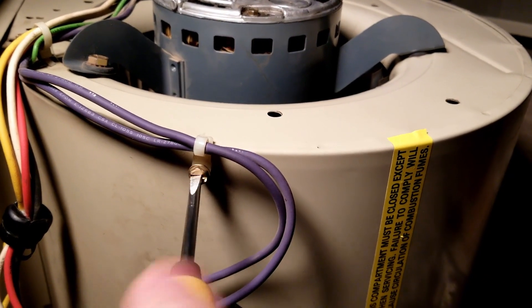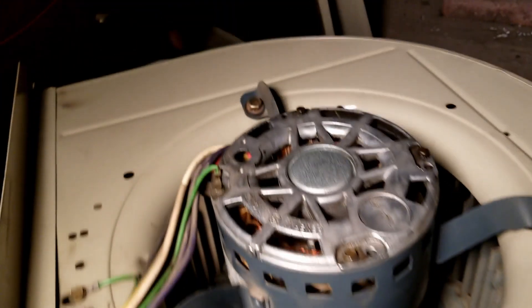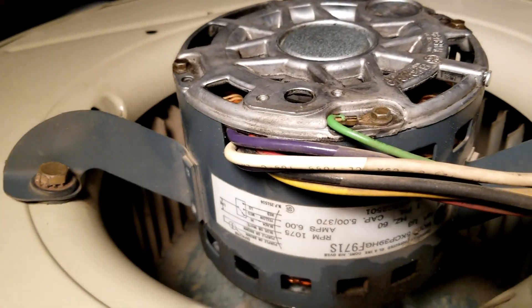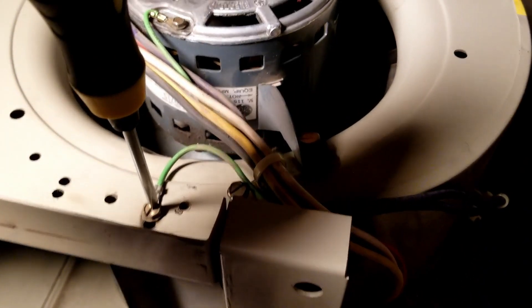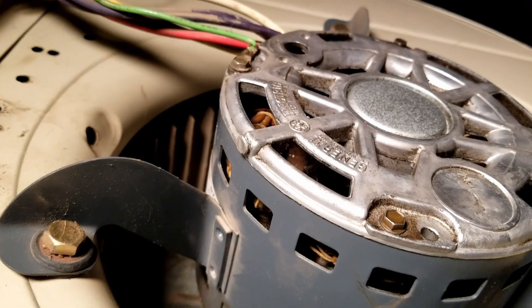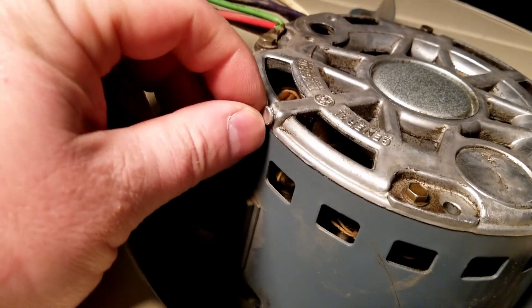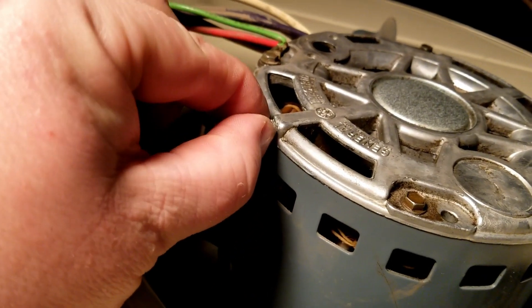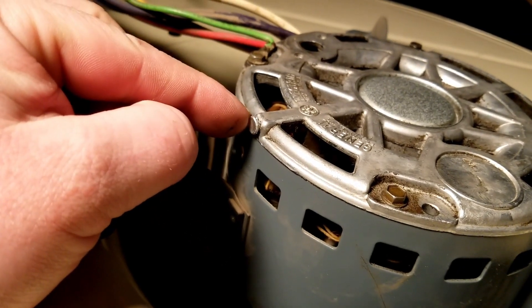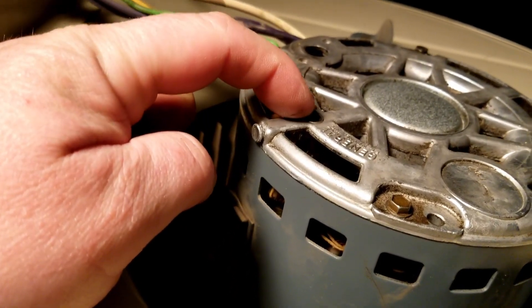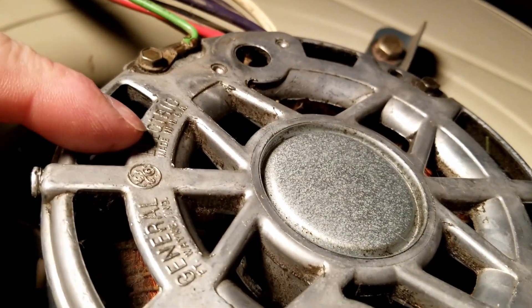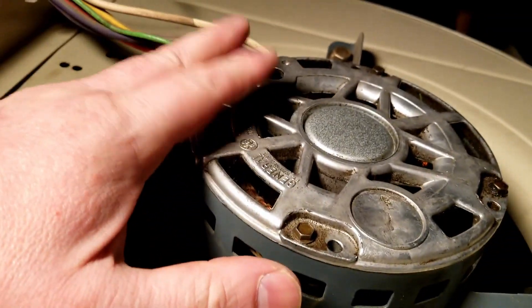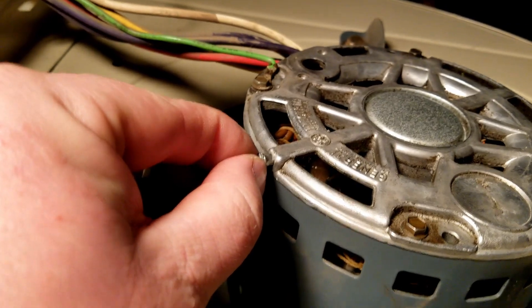We'll get these little Phillips screws out of the way because we'll have to get this wire harness off because it goes with the motor. It does not have a little connector to disconnect the harness, so all these wires go with the motor. And disconnect our ground, don't forget that guy. So this little cap here, this is where the motor gets oiled. You take this little cap out and there's a passage all the way through here to oil this bearing.